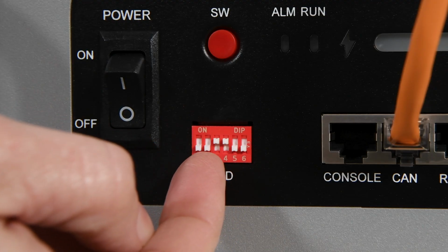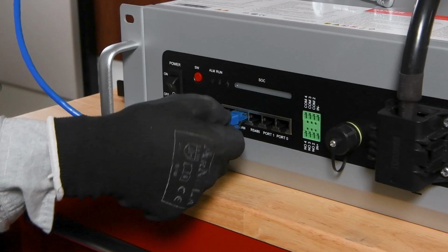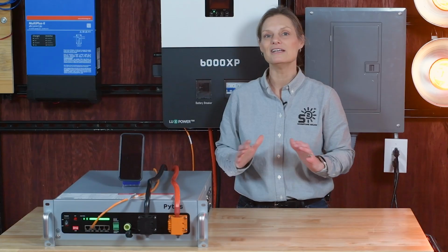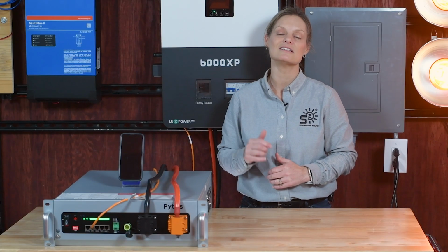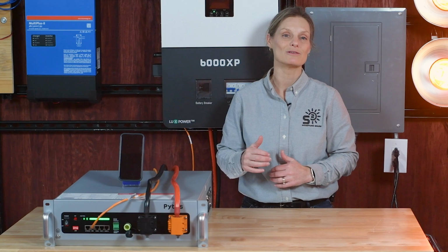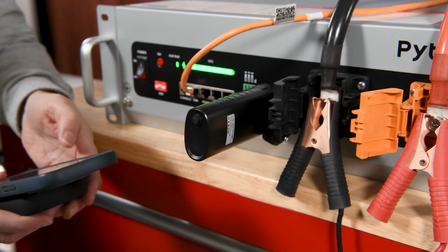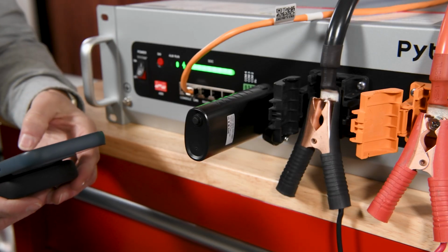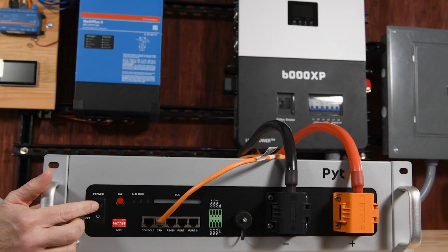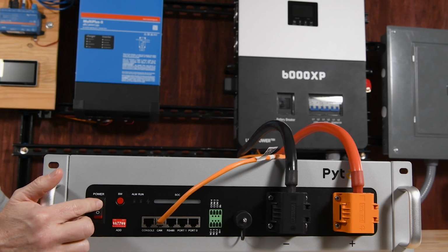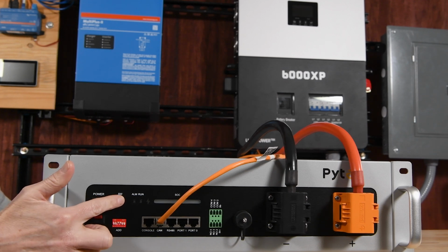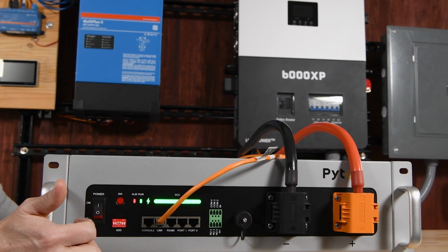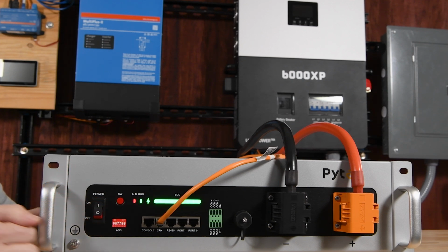The setup process is easy too. Just adjust a dip switch, connect the communication cable, and you're good to go. No need for complex configurations. It's simple, efficient, and reliable. During our test, we successfully connected the V5 to a Victron and an EG4 6000 XP inverter, showing how easy it is to set up. We used the soft start feature, set the dip switches, and the battery communicated seamlessly with both inverters without any issues.